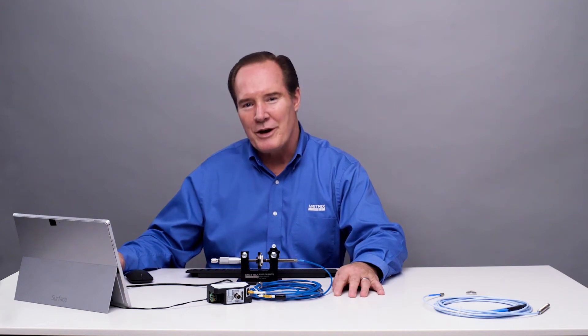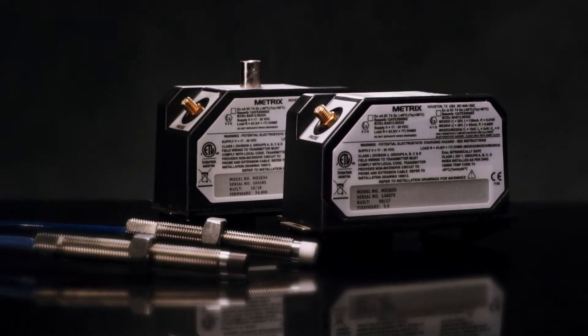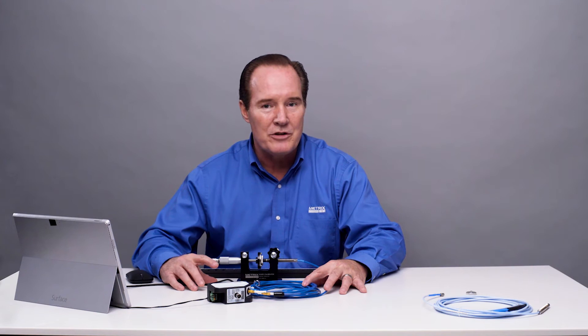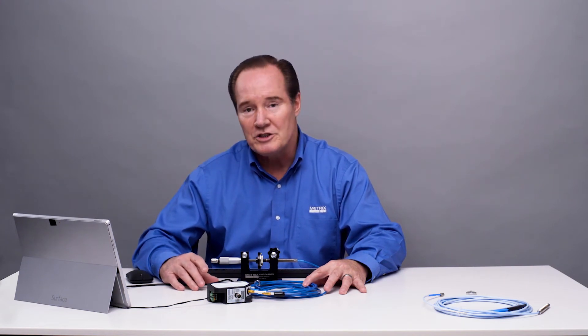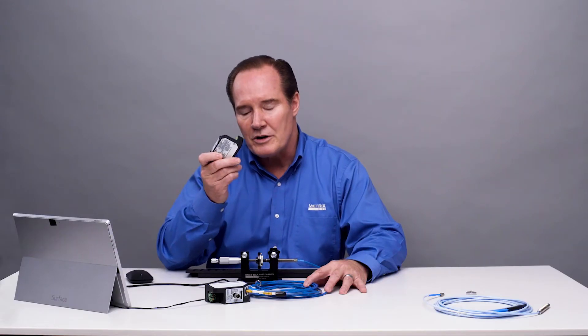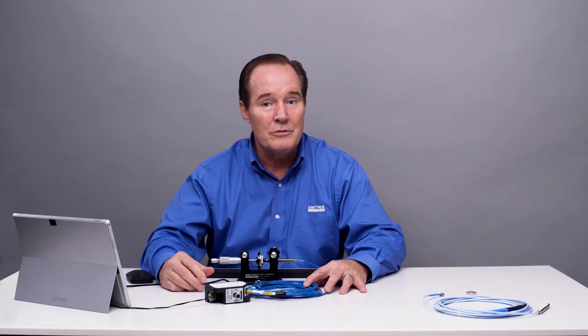My name is Rhett Jesse and today we're going to talk about the Metrix Digital Proximity System. Today's experiment, we're going to talk about changing from an MX8030 probe and cable system to a competitor's probe and cable system to see how the digital proximity system works. What's nice about the digital proximity system, whether it's an MX2034 transmitter or an MX2033 driver, is we can configure it for the probe and cable that we need it to work with.